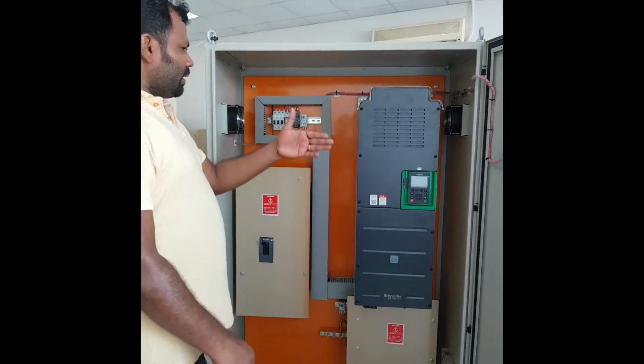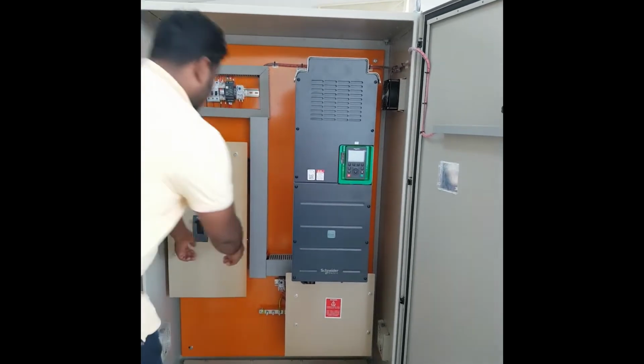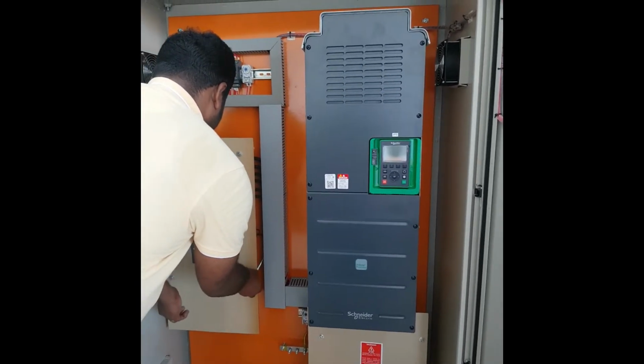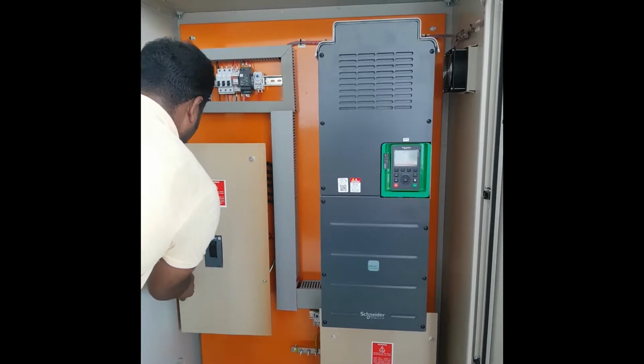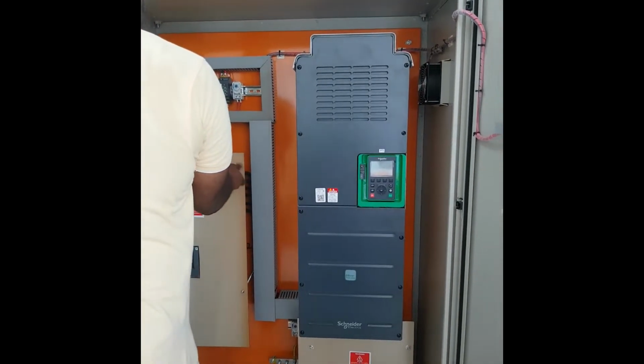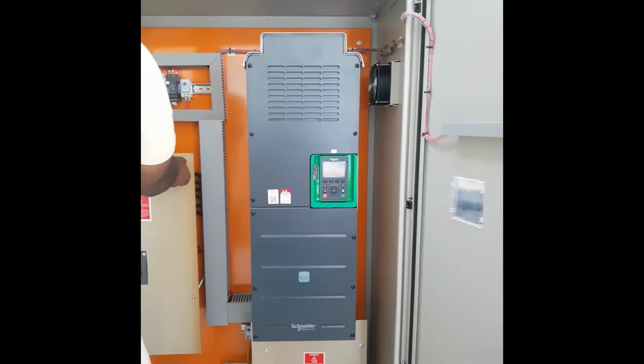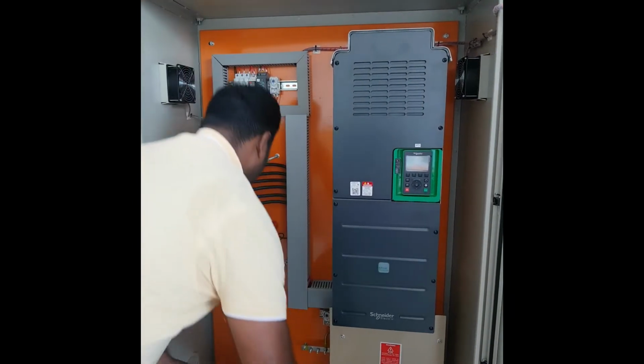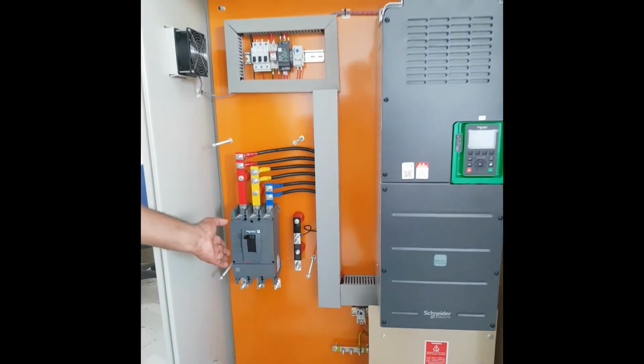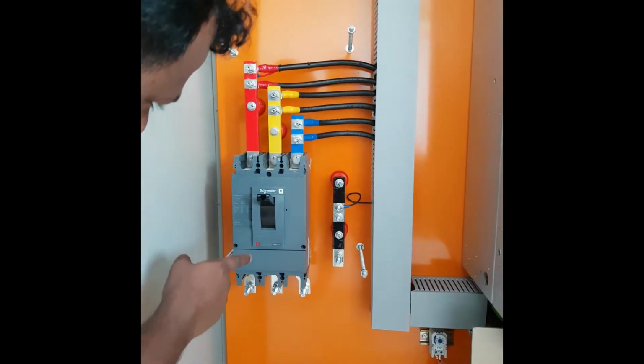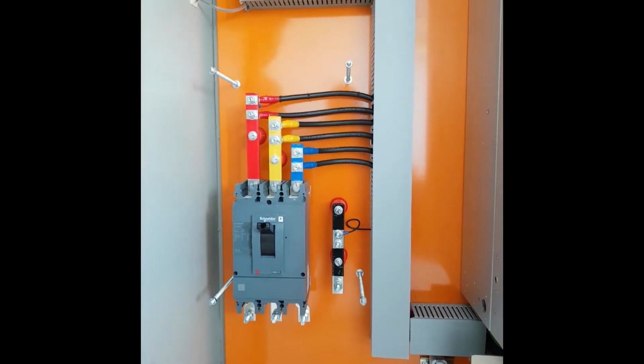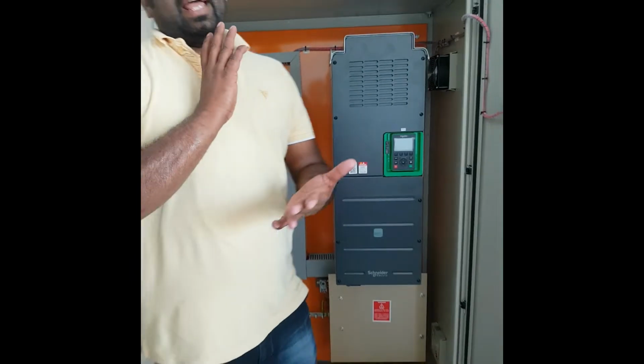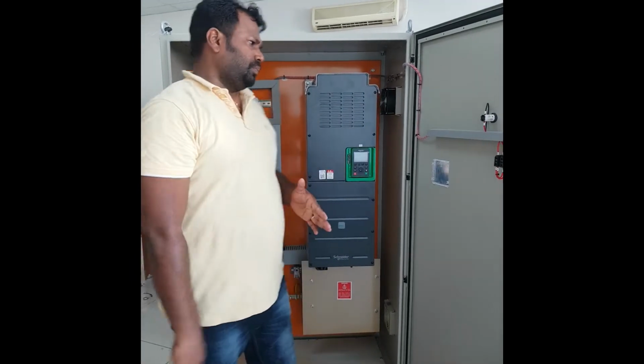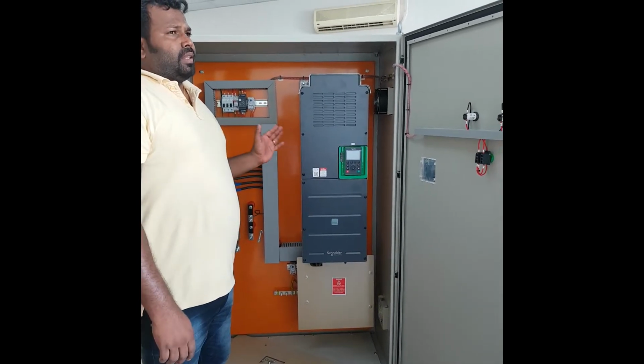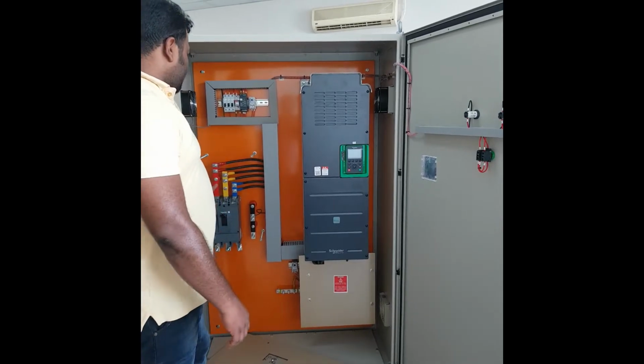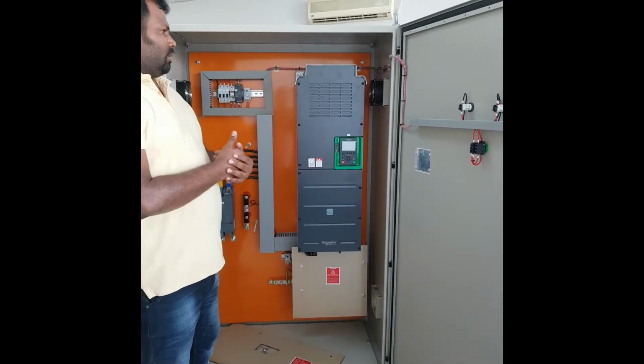Apart from this, we have given one incomer MCCB rated 400 ampere, also Schneider brand. This MCCB works as an isolator as well as short circuit protection equipment. Whenever there is a short circuit between this MCCB and the pump, the MCCB will act, trip the circuit and protect from the short circuit.